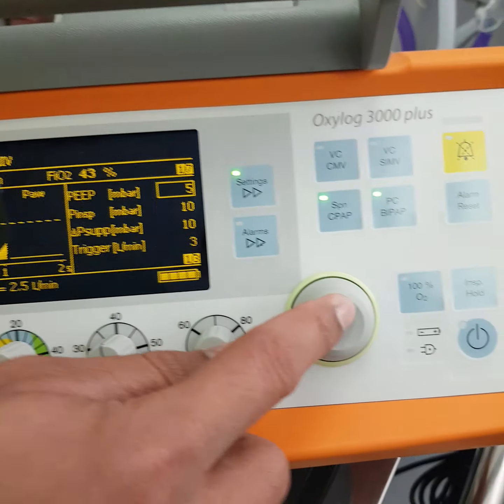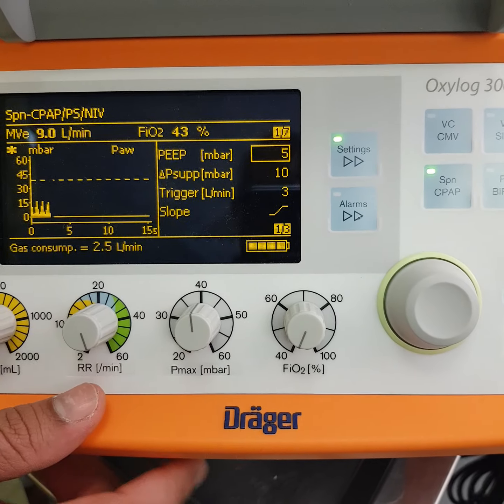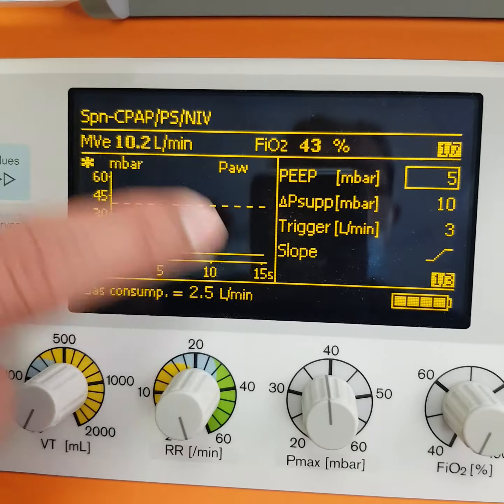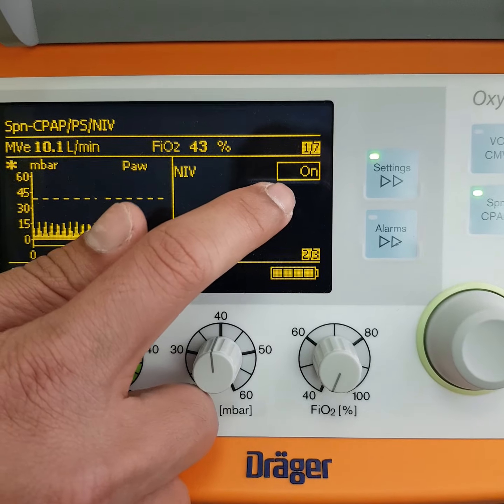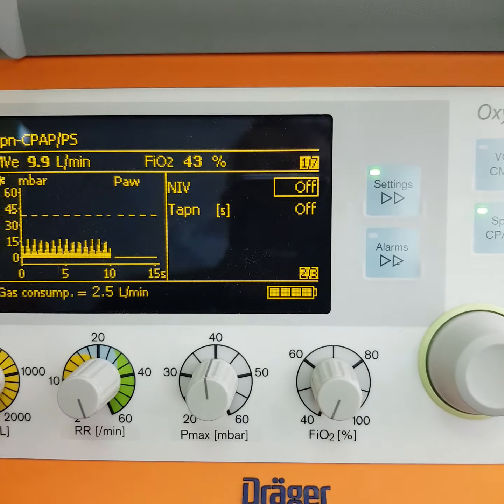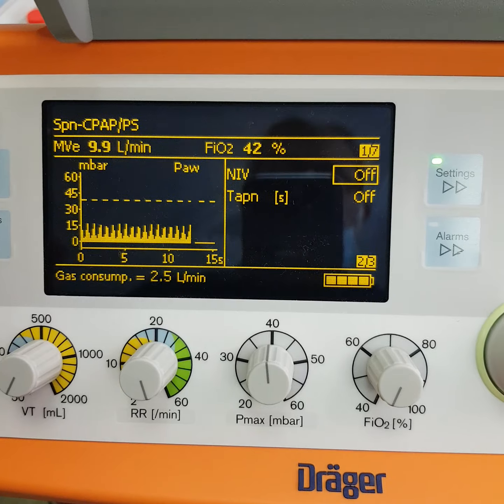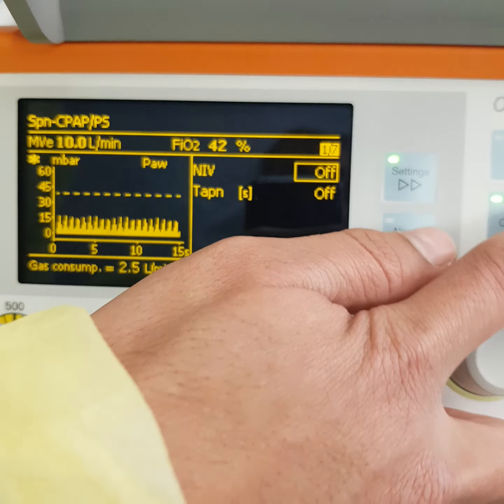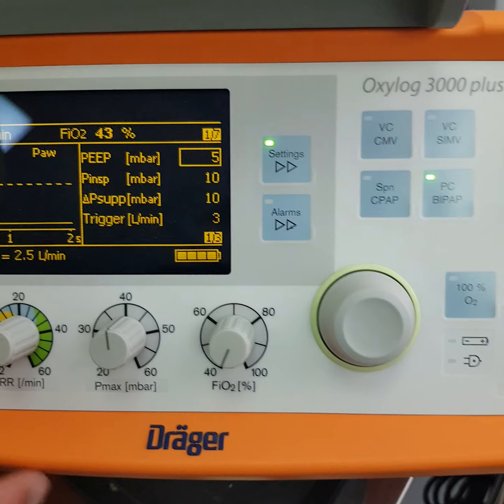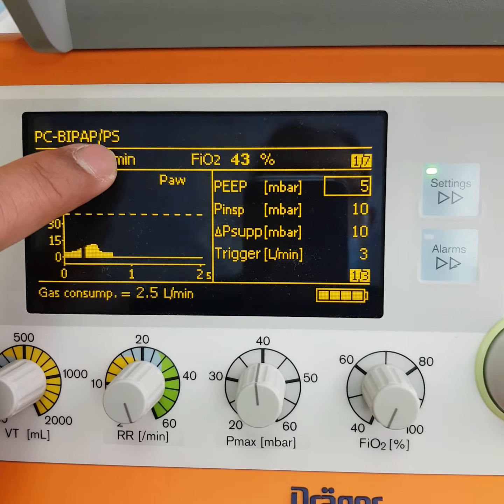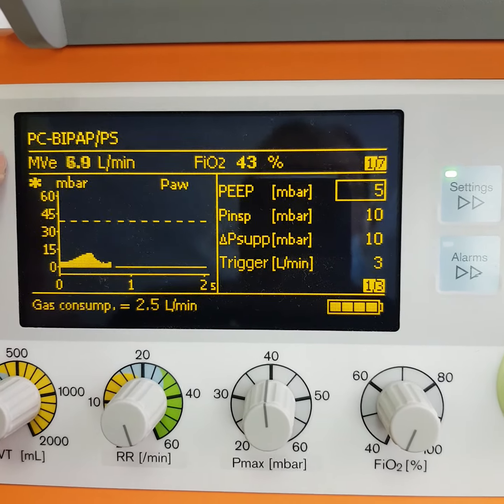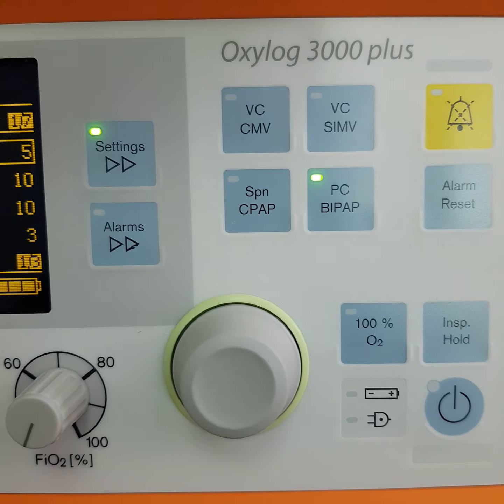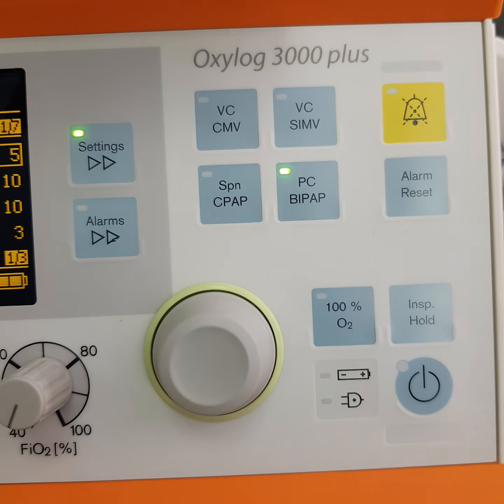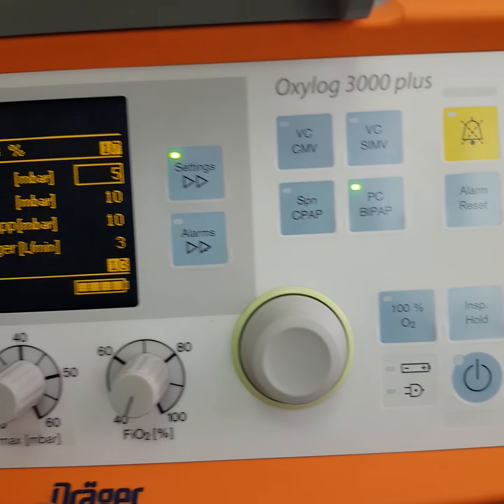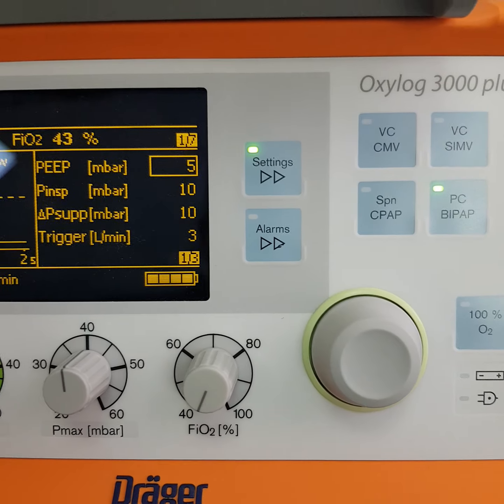So again, this CPAP mode also can be used as a non-invasive ventilation. The only thing is you have to activate NIV in the settings here, NIV on. If you make it off, that means you can use it for the invasive patient with a CPAP mode. Similar goes for the PC BiPAP. Right now it is not written NIV, so you can use it for the invasive patient. But all the four modes can be used as invasive ventilation unless you activate NIV for these two modes, and then you are going to connect the NIV mask with the circuit.